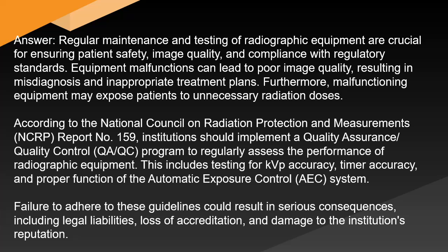According to the National Council on Radiation Protection and Measurements' NCRP Report No. 159, institutions should implement a quality assurance quality control (QA/QC) program to regularly assess the performance of radiographic equipment. This includes testing for kVp accuracy, timer accuracy, and proper function of the automatic exposure control (AEC) system.